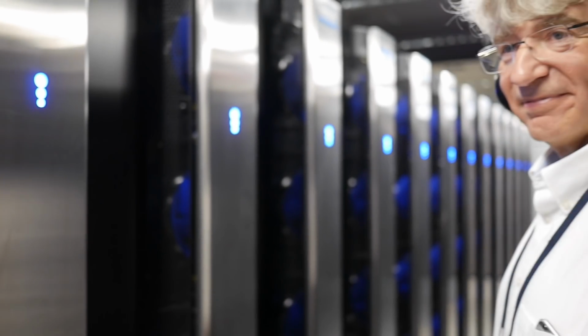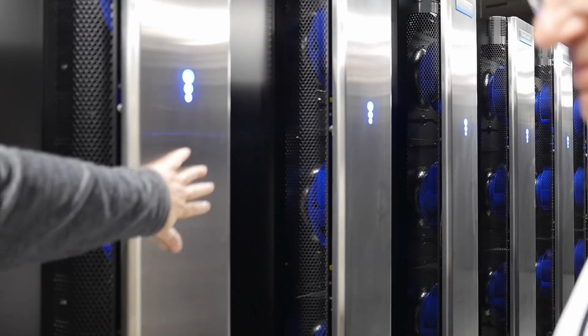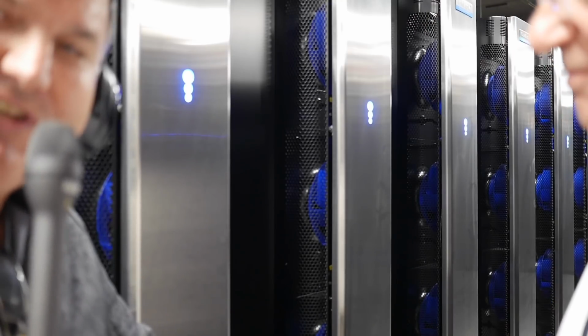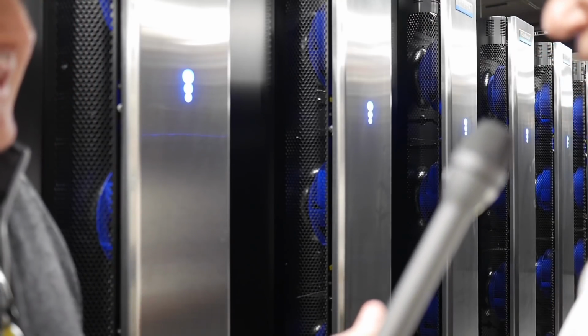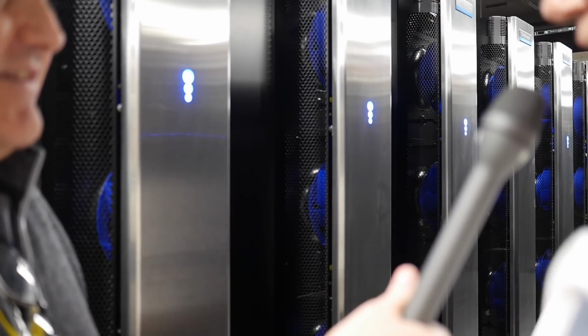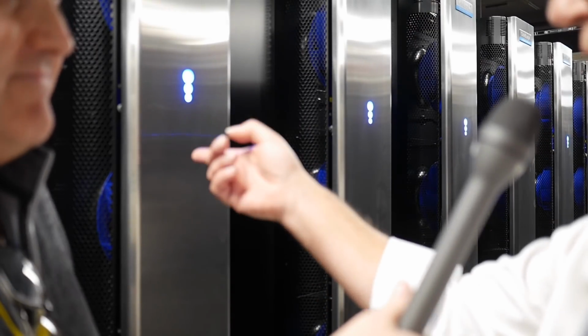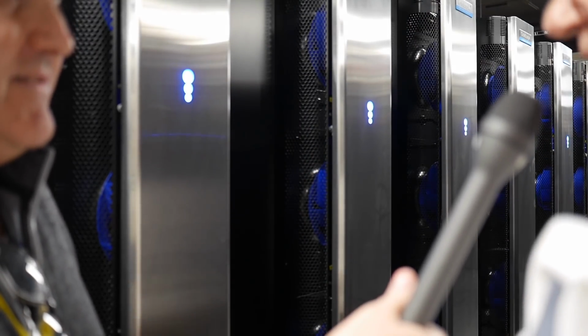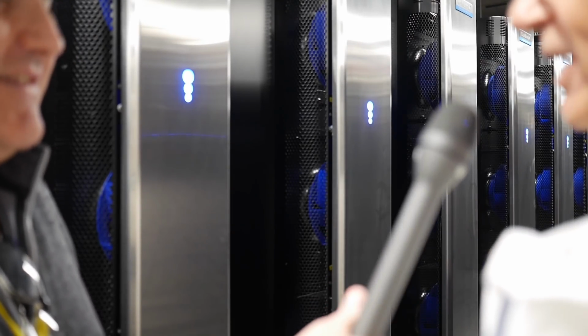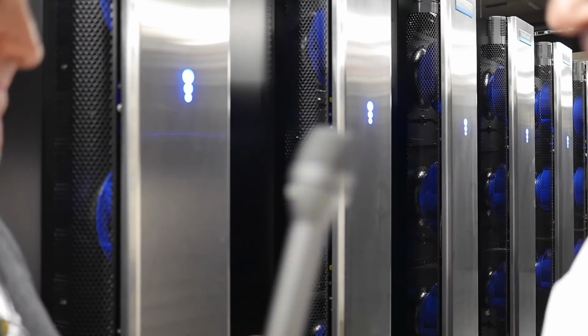What you're looking at here is the new fun toy in your data center, which is the water-cooled racks. These are fully water pumped, and they're chilled, and they're running chilled air around the data center. The theory here, well, in fact, we know it's true, is that we can put at least 30 kilowatts of rack through these, and probably a lot more than that. The air temperature going in on one side gets blown back out at exactly the same temperature, even with 30 kilowatts of rack inside. That's for the very dense compute for the whole data center, not just for JASMIN.